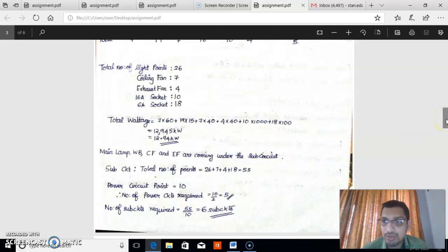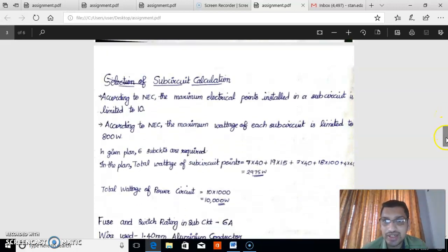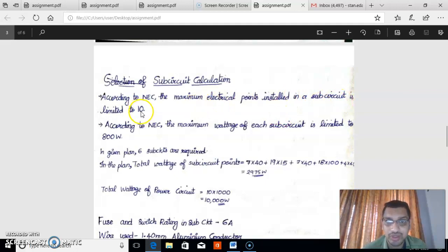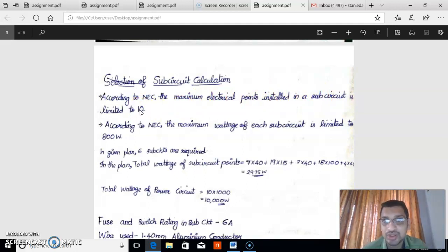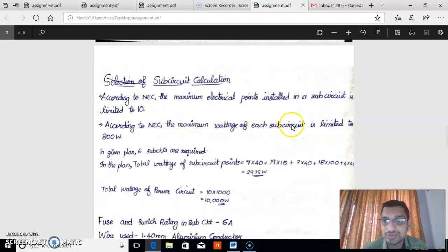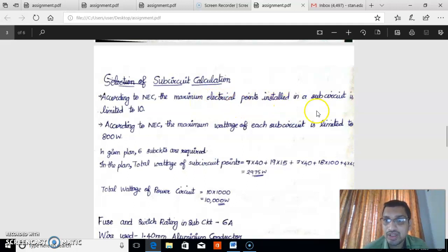For calculating the number of sub-circuits, there are two criteria. The first criterion, according to NEC, is that the maximum electrical points installed in a single sub-circuit is limited to 10. The second criterion is that the maximum wattage of each sub-circuit is limited to 800 watts. These are the criteria for selecting the number of sub-circuits.